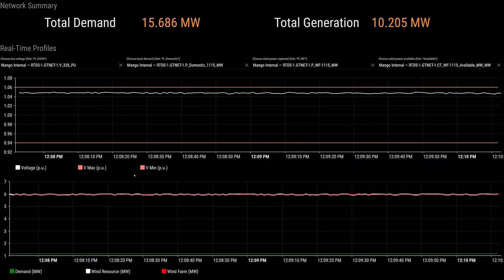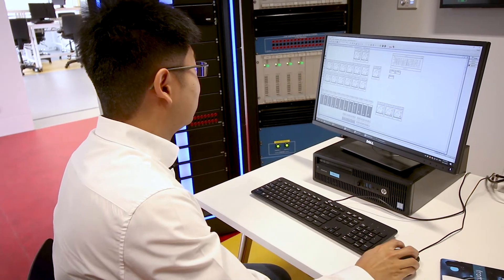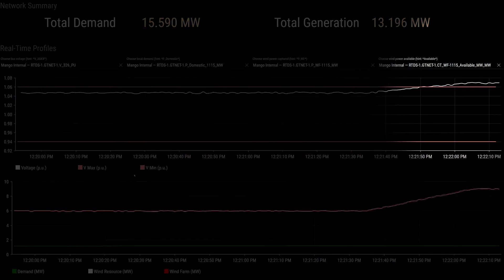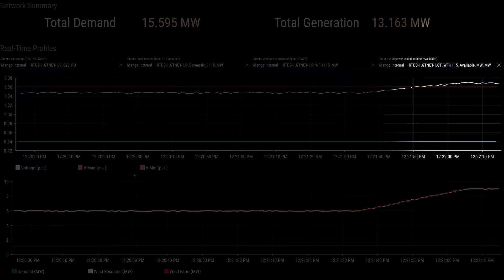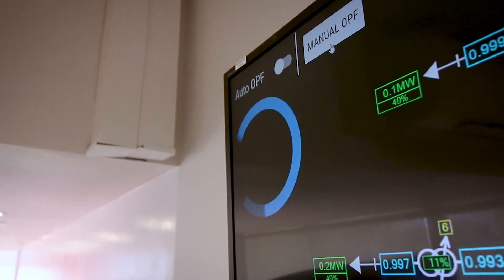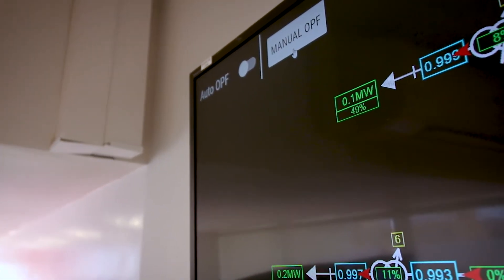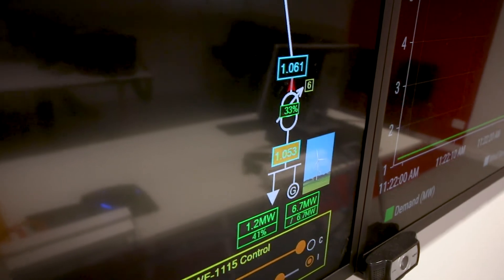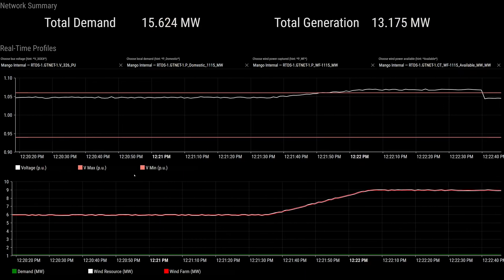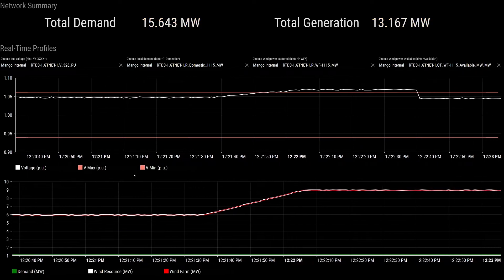To demonstrate our control algorithm I will introduce an artificial ramp in the wind speed. After introducing the ramp, the wind power will go up and eventually this voltage will exceed the statutory limits, indicated by this plot here as well as the flashing signals on the status screen. To address this problem I'm going to manually trigger the OPF. The system will run the optimization algorithm and calculate the new set points. As you can see, the power factor has changed for this wind farm and this new power factor addresses the voltage problems we had previously.